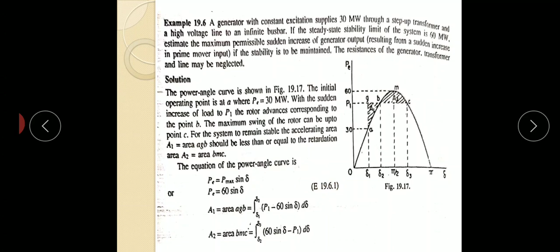So applying area A1 equal to A2, and finally applying these conditions, at point A, P equal to 30 and delta equal to delta 1. At point B, P1 equal to 60 sin delta 2, same as the previous example. After solving, we get delta 2 equal to 60.4 degree. Simple mathematics here. And finally, the maximum permissible sudden increase of load, what is the value here? P1 is equal to 52.17 megawatt.